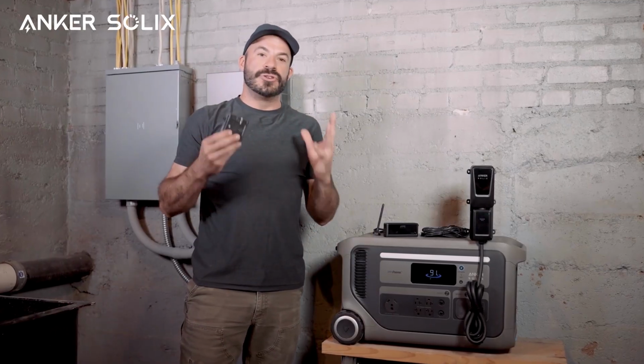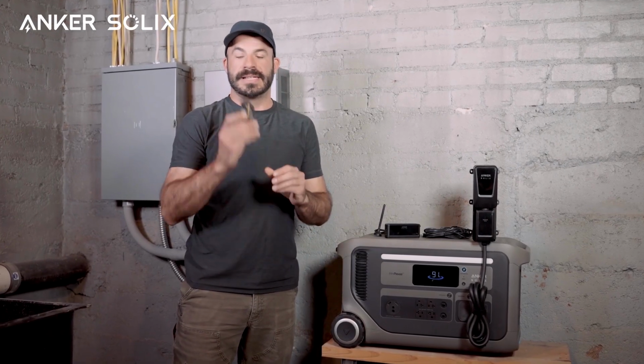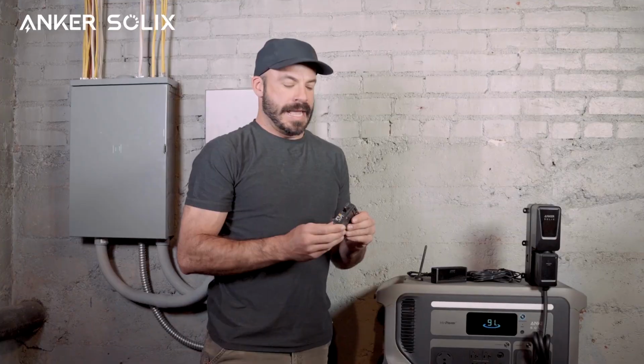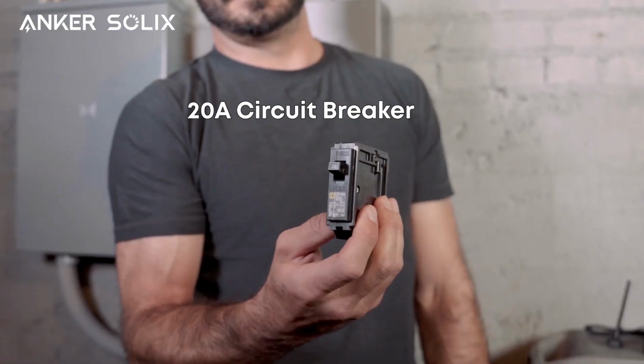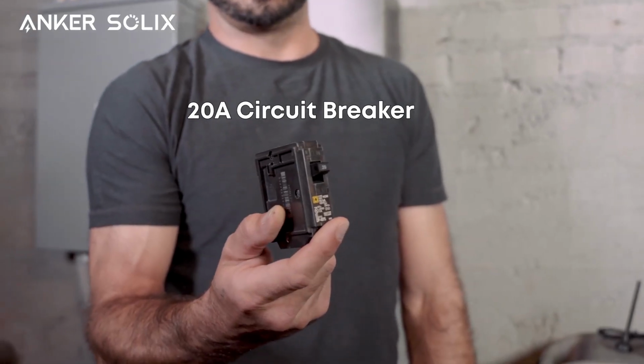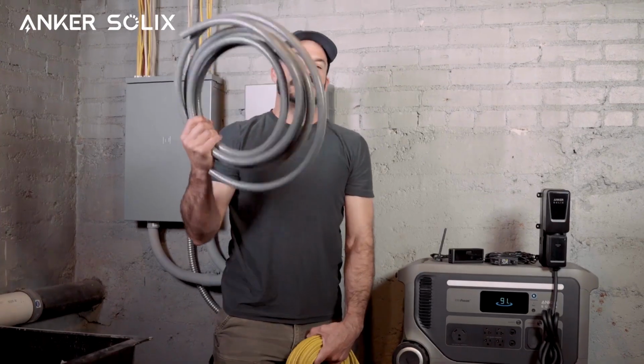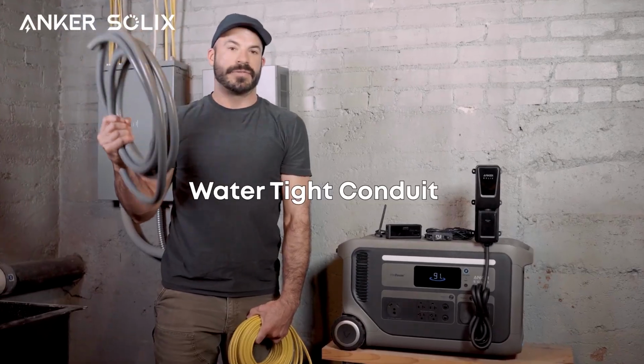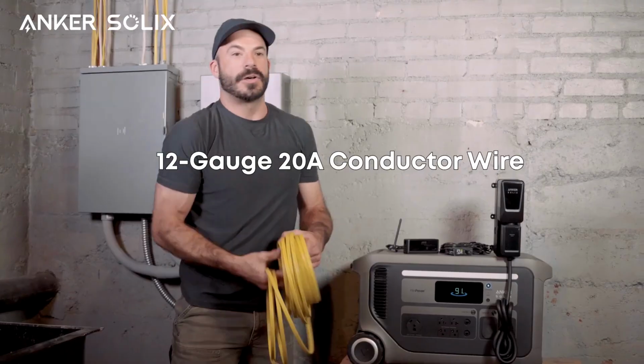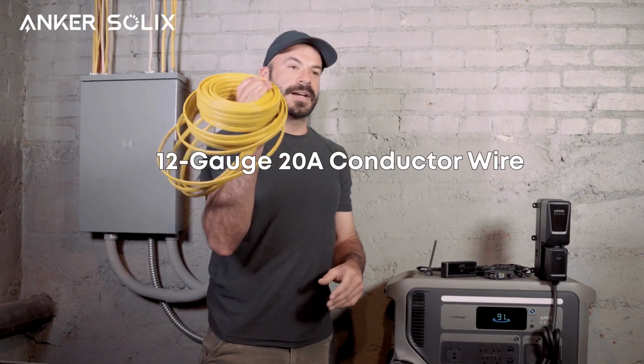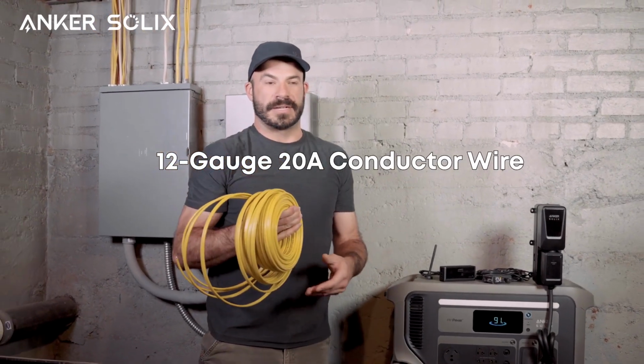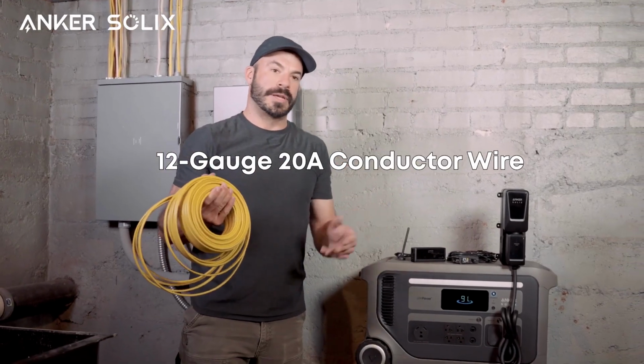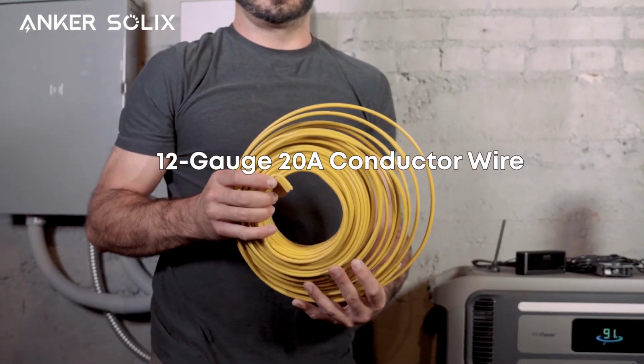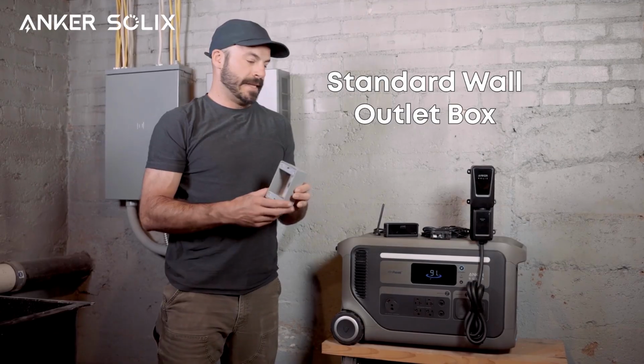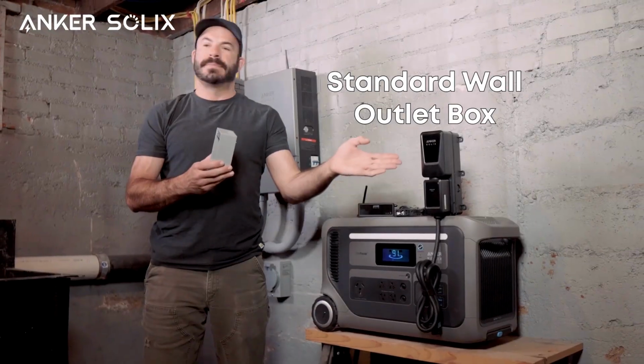For installing this in a new circuit, you'll need a circuit breaker for that location, with a minimum ampacity we recommend of 20 amps. This is a 20 amp circuit breaker compatible with my home's breaker panel. You'll also want watertight conduit for installing the new circuit, along with appropriately sized conductors for taking power to and from that circuit. In our case, for a 20 amp circuit, we're using 12 gauge wire.